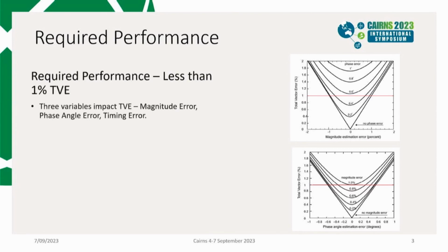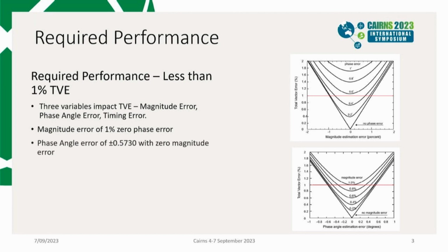Required performance in order to meet the PMU standard is quite arduous, and so there was a considerable amount of research that went into understanding whether the existing assets on the distribution network would be able to achieve this. On the right-hand side there, you can see a couple of graphs which show the required performance of less than 1% total vector error. And there are three different variables that impact that, being magnitude, phase angle error, and the timing error. So those graphs show the tolerances available in the other two domains if you hold one of them constant.